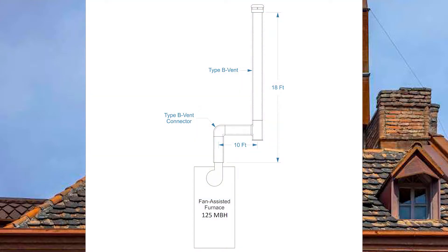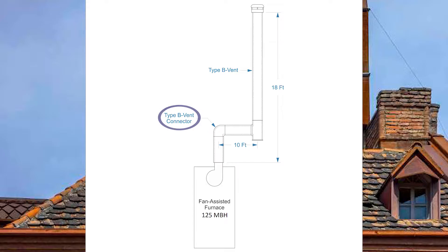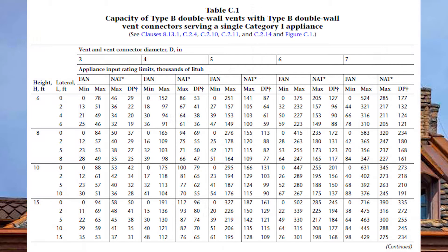The easiest way to do this is to go through an example. I have a 125,000 BTU fan-assisted furnace with a 10-foot vent connector lateral and the vent itself is 18 feet tall. Both the vent and vent connector are double wall or B vent. When we turn to Table C1 to size this up, we very quickly notice there is no 18-foot vent height designation.